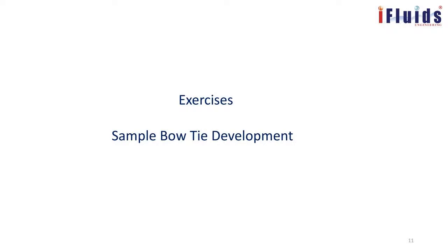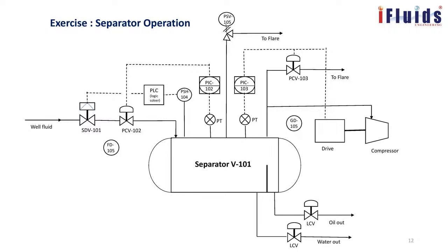Now we go into the exercise — the main objective of today's training. We will look at a three-phase separator in an oil and gas field, which is a pressurized vessel. Well fluid from an oil well — containing oil, gas, and water — enters from the left. Inside the separator, oil, water, and gas are separated. The liberated gas goes to a compressor, while oil and water settle based on density — oil floats and is taken over a weir plate, water is taken from the bottom through a control valve for further processing.